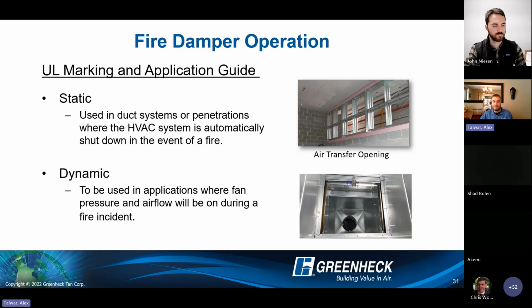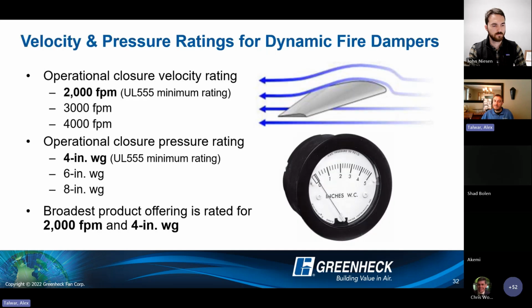Otherwise, if there will be fan pressure or airflow that may be on during a fire incident, we'll need a dynamic rated product, and we'll need to have these dynamic ratings. So velocity ratings established every 1,000 feet per minute, starting at a minimum of 2,000 feet per minute. And that's established when the damper is in the open position. And then the pressure rating when the damper is closed, to be able to withstand those pressures listed there, minimum of 4-inch water gauge, and then in increments of 2 inches above that. So again, to avoid overspecking, word of caution, broadest product offering is always available at the lowest ratings.